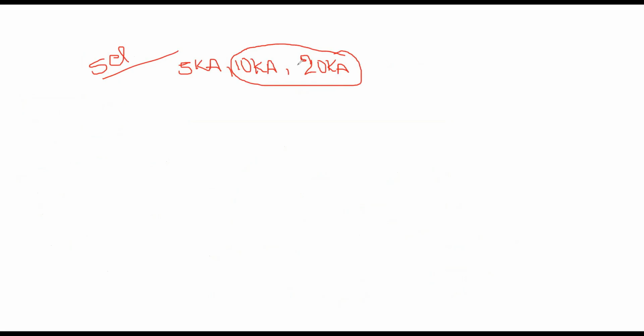Let's suppose, in a simple way, if I am selecting a 5 kA lightning arrestor and testing its operating principle, then the high current impulse of 65 kA we apply 2 times, and 20 times the basic lightning impulse of 5 kA, and we check whether it stands or not.